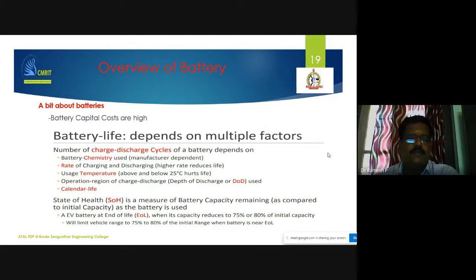Battery chemistry depends upon the manufacturer. The rate of charging and discharging is very important, whether you use fast or slow charging technology, and similarly for discharging. If you go with higher charging and discharging rates, it reduces the life of the battery. Also, using temperatures above or below 25 degrees centigrade adds to battery degradation, but in the worst case, don't go more than 40 degrees centigrade.